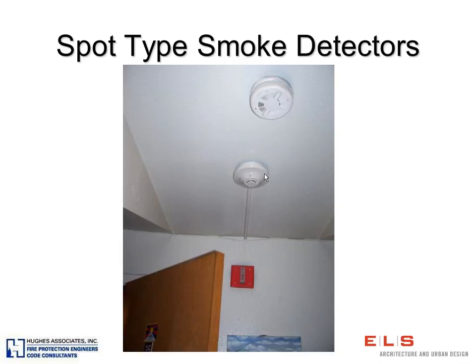This is interconnected with a fire alarm system, so it's a low voltage smoke detector, and you can see in this particular application you have exposed conduit that's running back out to the fire alarm system. This particular sleeping room is a room for the hearing impaired, because you can see that we've added also a strobe device or a visual notification appliance directly within the sleeping room to accommodate a hearing impaired individual that may be present within this room.